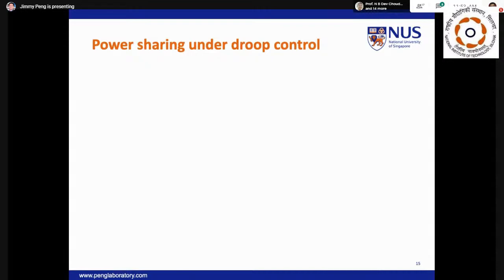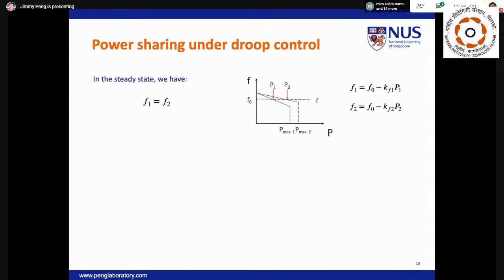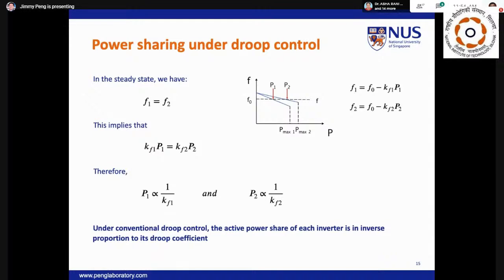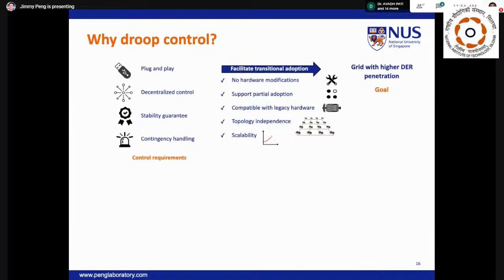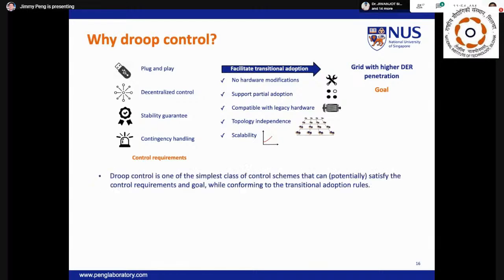Suppose we now have two inverters regulating the grid frequency. Under steady state, F1 equals F2. This implies that KF1 times P1 will equal KF2 times P2. Now, by rearranging the relationship, we can conclude that the active power shared by each inverter is inversely proportional to its Droop coefficients. There are other options for decentralized power sharing, but Droop control is perhaps the simplest, and its principles are analogous to those used in the governor system of synchronous generators.